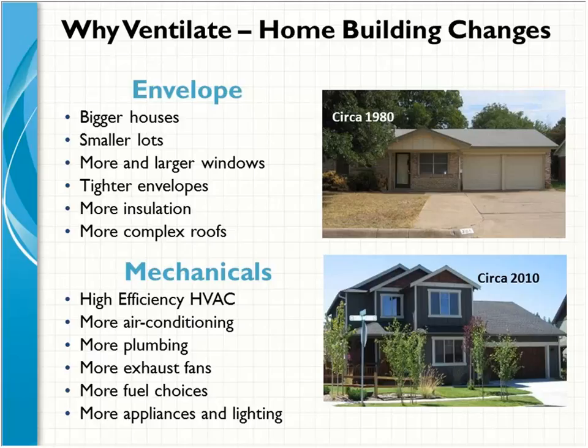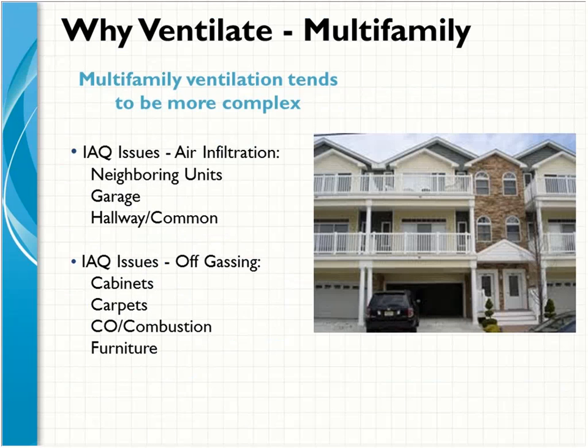And as far as the mechanical systems, a lot has changed there as well. And this is a question that I'd like you guys to answer if you can. Where did the combustion air for the furnace come from 30 years ago? Exactly. It came from inside the home. It was sucked in through the mechanical room, into the furnace, through the combustion chamber, and out the chimney. Well, that was ventilation. That was forced ventilation in the home. And today, we suck that air through a plastic tube into the furnace. It goes through the combustion chamber and gets blown back out. So even that ventilation, in addition to sealing up the home and making it more airtight, we've eliminated some of the ventilation that the furnaces used to provide. So we have to do something to make up for that.